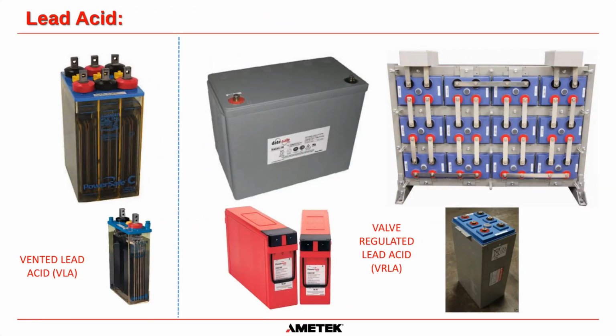And then on the left-hand side, we have 2 examples of what a vented lead acid cell, or a VLA, is. And basically, if you can see the electrolyte inside a lead acid cell, that makes it a vented lead acid cell. Okay, and on the right-hand side here, you can see many different versions of what a valve-regulated lead acid battery, or a VRLA battery, looks like. Now, bear in mind the chemical reaction in both of these batteries is identical.